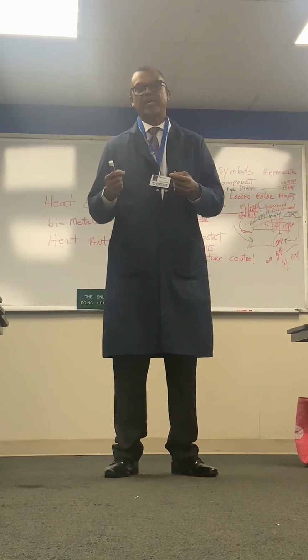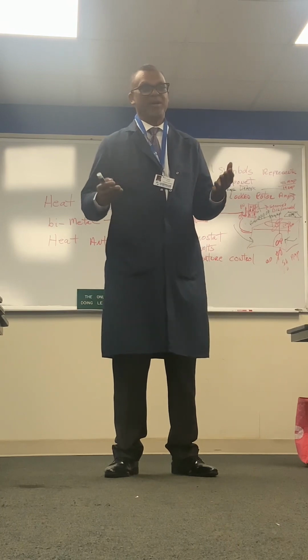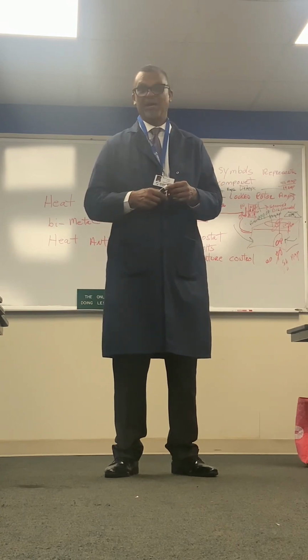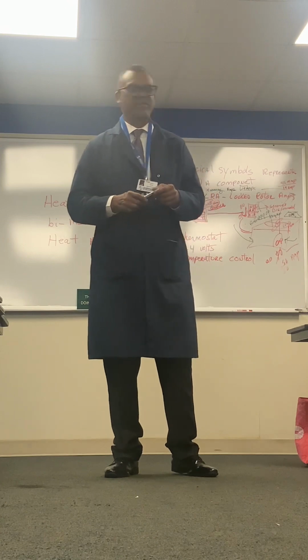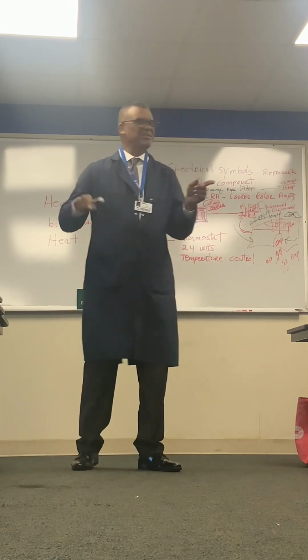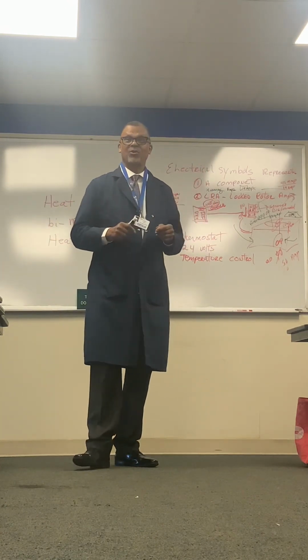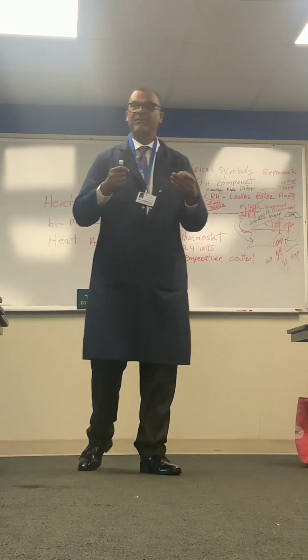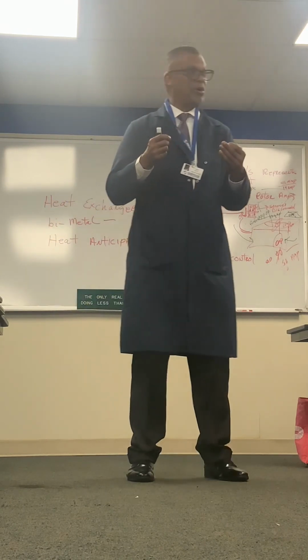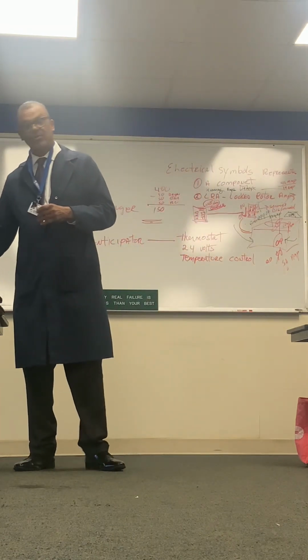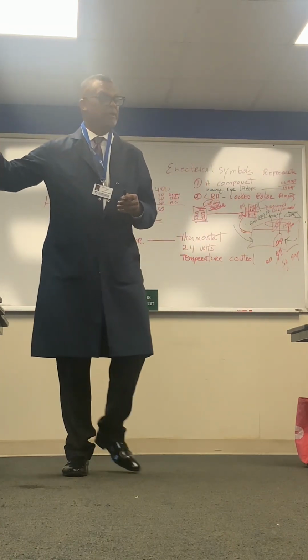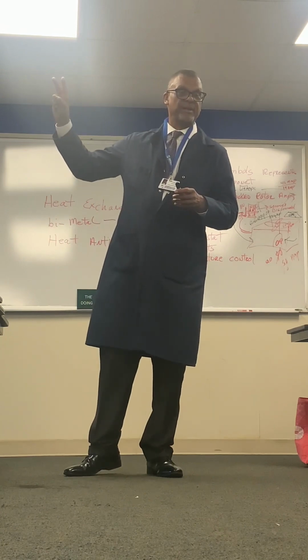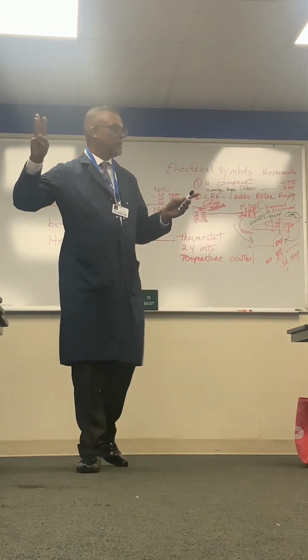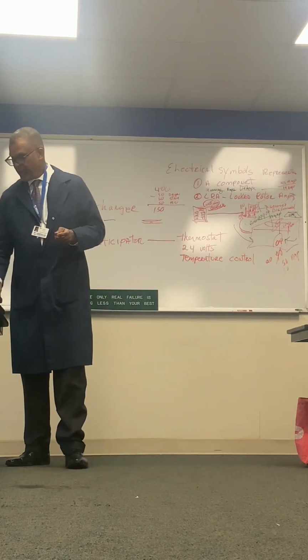Okay, so if you had a said transformer, and I say, because I'm interviewing, remember, I do everybody like this on an interview. I don't say you're wrong. I say explain that, because everybody doesn't think like me. None of us think the same. And if you had told me, well, if I have 24 volts in my control system, it will, when energized through, you told me red, what, for AC? Yellow. Yellow, and what else? Green for the indoor fan.